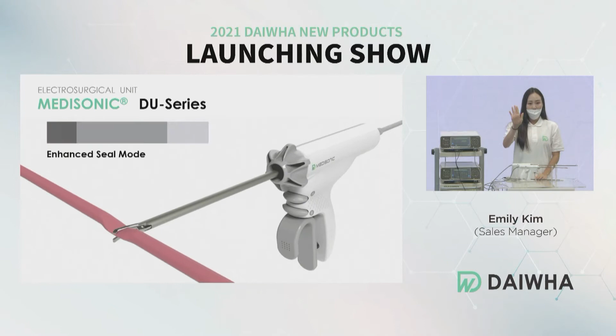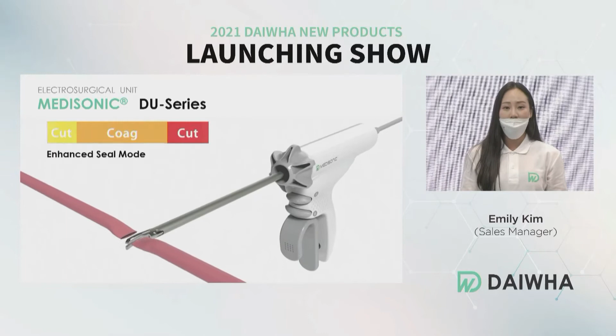Ultrasonic energy device is usually applicable up to 5 millimeter vessel. You may recognize that most of surgeons do not try to seal larger than 5 millimeter vessel only with energy device for safety. However, you can cut and seal up to 7 millimeter vessel with a Medisonic enhanced seal mode, just as an advanced hemostasis mode of harmonic scalpel. This is our DU series simple specification.